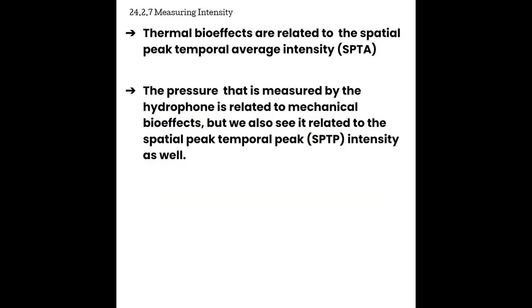So you may have noticed that as I was discussing these tools that you can either measure the total power in the beam or measure at very specific locations. When we talked about measuring intensities, we learned that intensity changes based on the spatial considerations, either being in the very middle of the beam or towards the edge, which helped us define the average. We know that the middle of the beam is the most intense where we have the least intensity at the edge. The tools that can measure specific locations in the beam help to calculate that spatial intensity. By observing the beam over time, we know what the temporal considerations are and those can be measured as well.